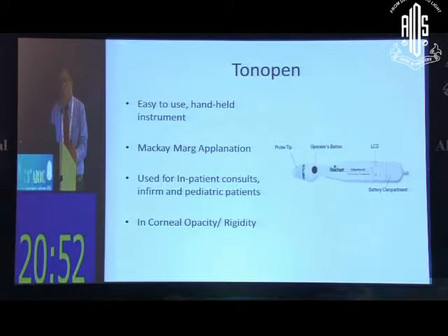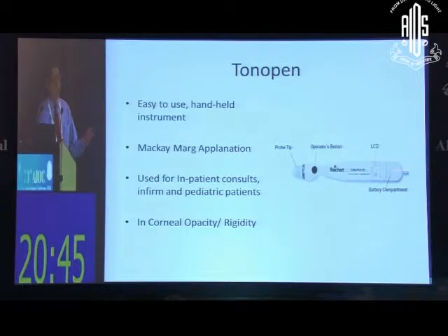Just one slide about the Tono-Pen. It belongs to the Mackay-Marg applanation category. This is what it looks like, and the advantages are two. Because it's portable, you can use it for EUAs and also in your in-ward consults. And also, arguably, it is the best tonometer to use over corneal opacities to record the IOP.